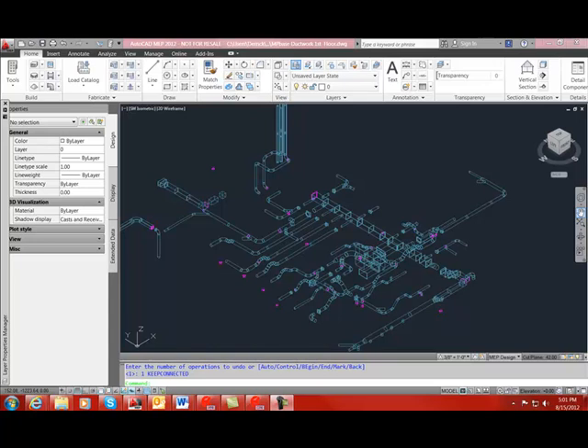Running the Duct Break command will break up your ductwork into fabricatable sections. After breaking up your ductwork, however, you will need to review your taps to make sure that none of them have been placed on a joint. You should review each system for this situation and either move the tap, move a short piece in a run to change the location of joints, or change some duct sizes to move the location of joints.